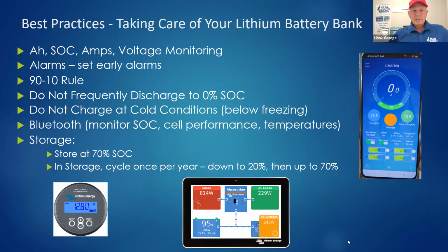But another good practice is, let me go back to the first bullet on amp hours, state of charge, amps, and voltage on your monitoring device. You'll want to pay attention to that as you're cruising, because with lithium, primarily you should look at amp hours and state of charge. The voltage discharge curve with lithium is so flat that we can't do what we used to do and say, oh, I discharged all the way down to 12.3 and now I'm going to start my charging devices. Well, in lithium, you're going to be in the 13s most of the time, not the 12s. And it's going to be most of the time between 13.2 and 13.4 something. So you're having to memorize state of charge versus second and third decimal places on your voltage reading.